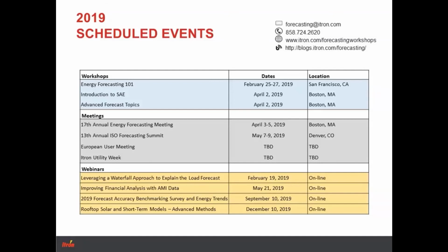Good question. Absolutely. It's kind of interesting, a little side story. The models that we build for the Australian market operator have the school holidays embedded in them, and it's because most of the country follows the same schedule, and that schedule is year round. So it makes a big difference when the kids are in school versus not in school. So yes, in fact we break it down between a winter schedule, a spring schedule, summer and fall schedule, because you're in different parts of the year with different weather, the coefficients on those will vary depending on which part of the year. So that's how we play out the school holiday.